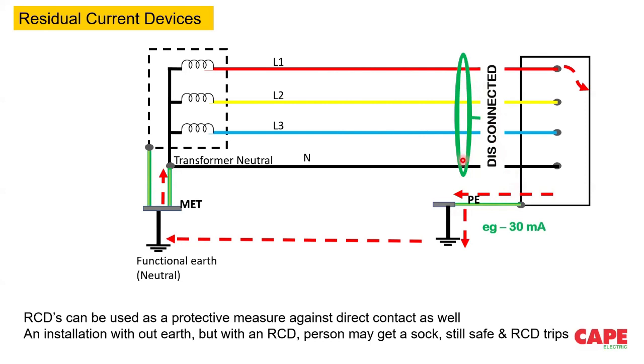You have a good RCD and there is a fault, the device will not trip in normal condition. But as soon as somebody touches the body of this equipment, then this device will trip. As a result, the person is safe against shock. Of course, he will get a small shock, but that shock is not strong enough to create a big problem.